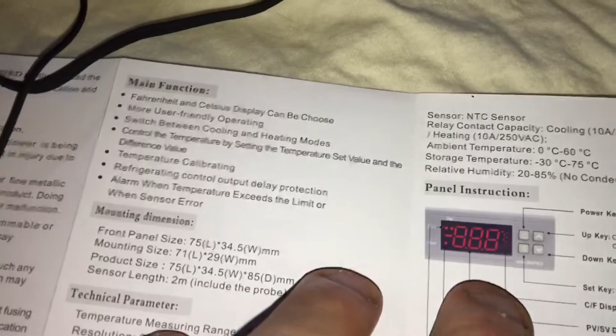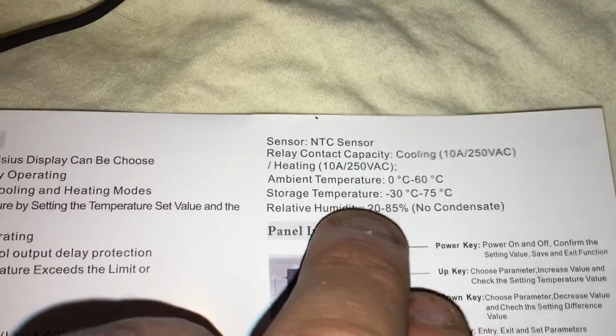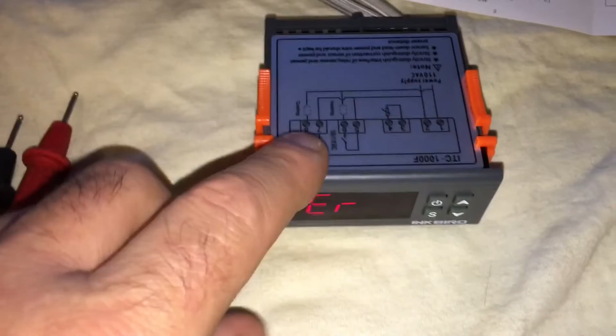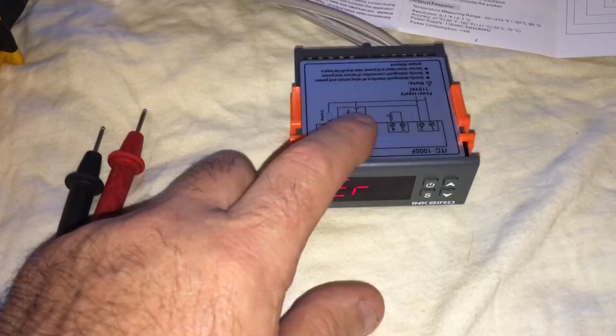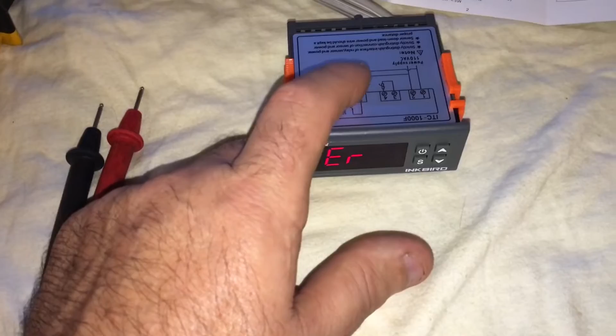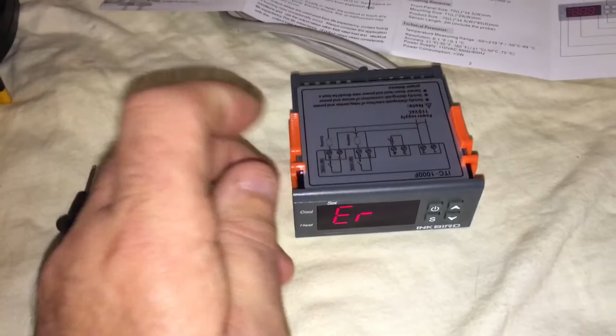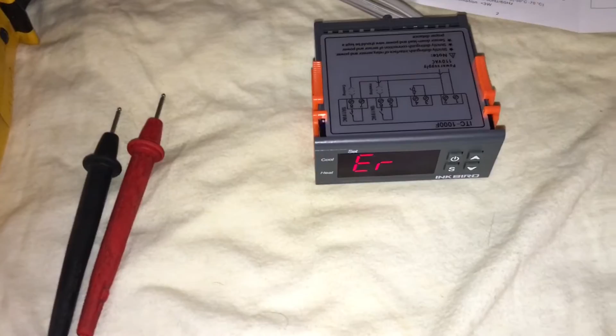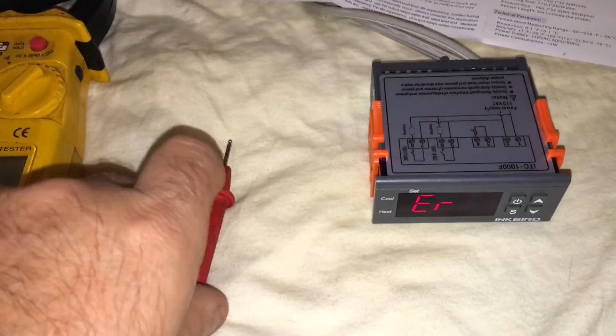I know the relays are only good for 10 amps, so you want to use an external relay with this, and you always should anyhow. With a digital temperature controller, just get in the habit of always using an external relay or a contactor, so you don't blow up your controllers, because it's only 10 amps. Any compressor draws like 7 times run load on startup, and it's not going to handle that. So just use an external relay, or a contactor is even better. Use yourself a 30 amp contactor for little refrigerators and you'll be whistling Dixie. It's the best way to go all the time.